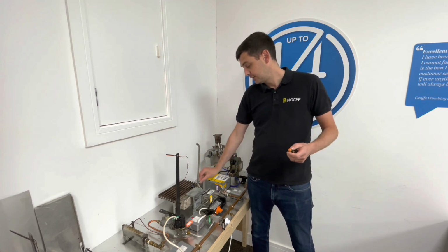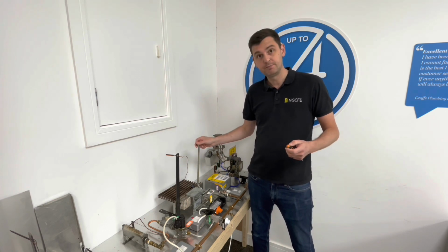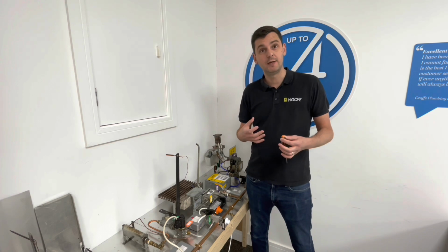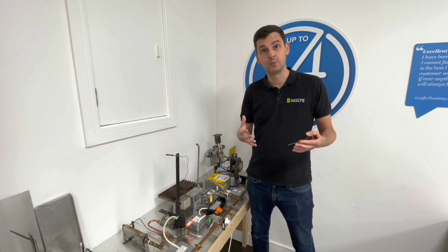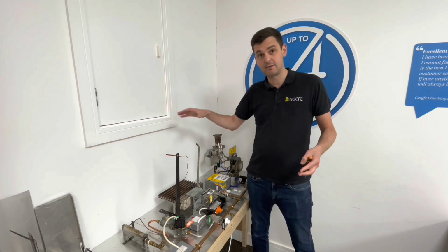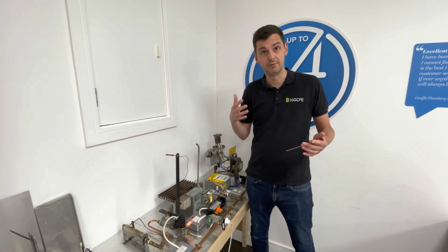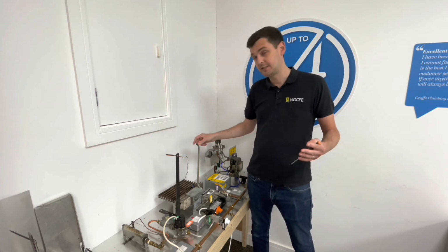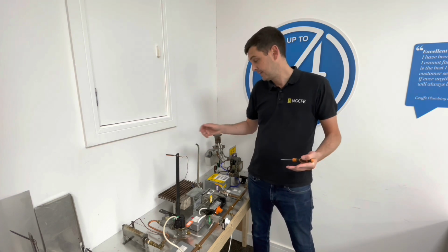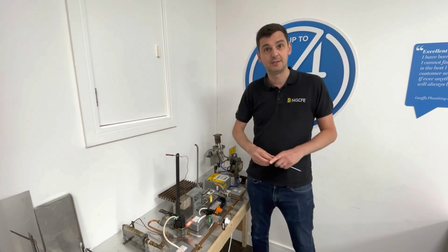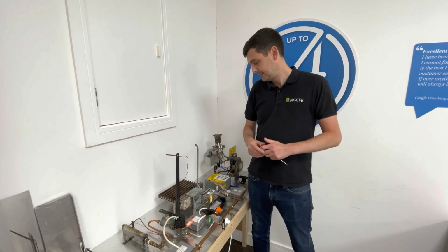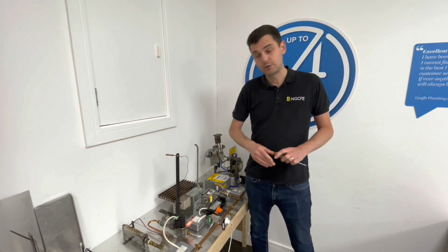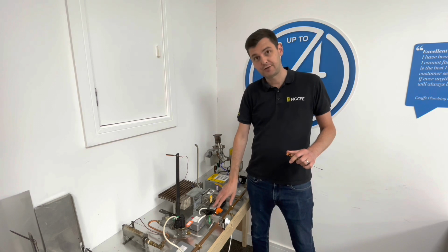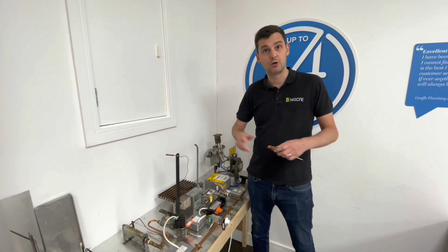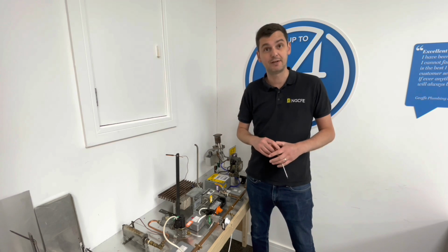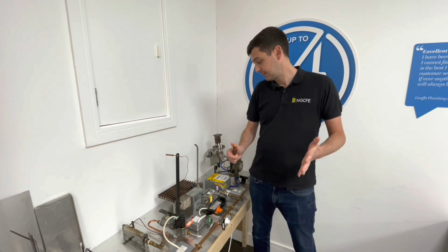If for whatever reason you do that and it stays blue, that would indicate that there's a break in it somewhere. The pilot light's getting its air for combustion from somewhere else. In which case, if the air above the burner was vitiated, when it wasn't meant to be, it's the job of the ODS to pick it up. It's not doing that, and again, that's a safety device that's non-operable, so that would be ID as well. So yeah, we've looked at the multifunctional control valve, the electric thermostat, and we've just looked at an ODS as well, an oxygen depletion sensor, which is pretty much the same as an atmospheric sensing device. That's it for that one.